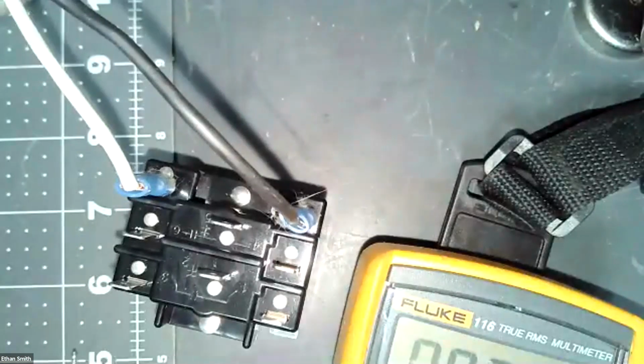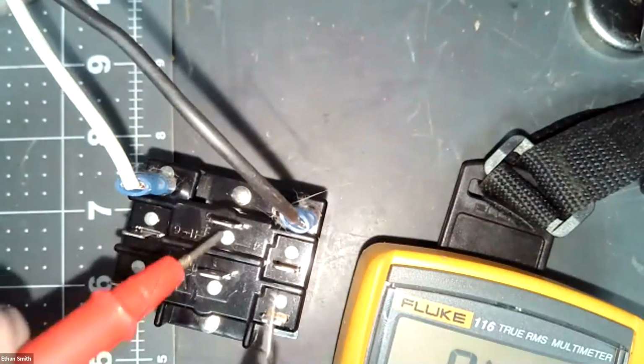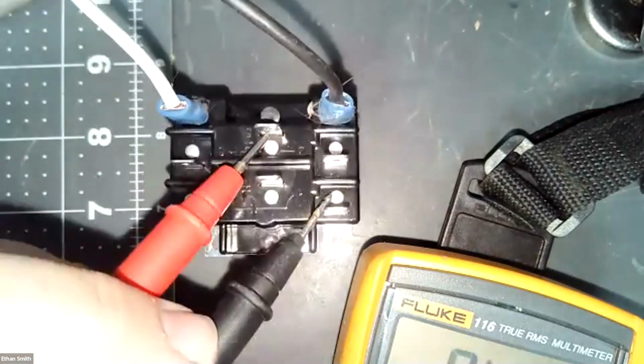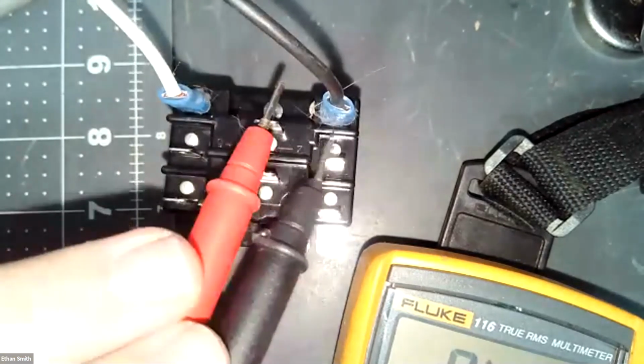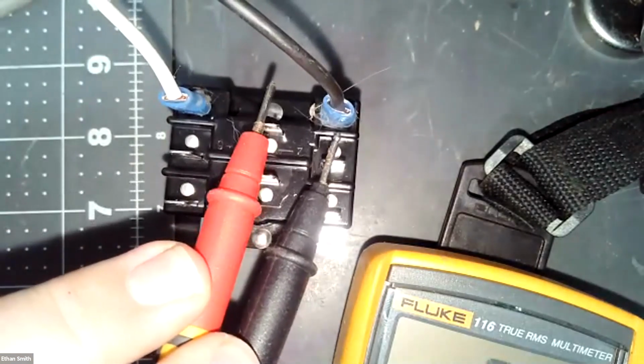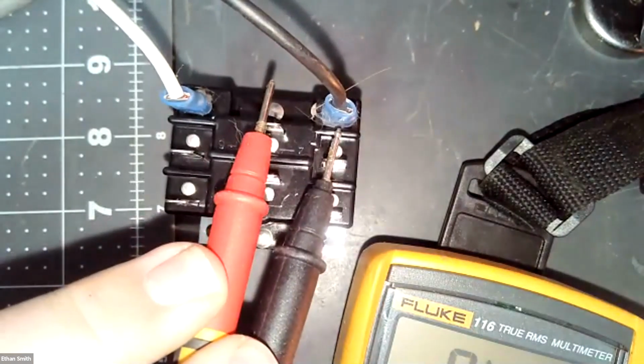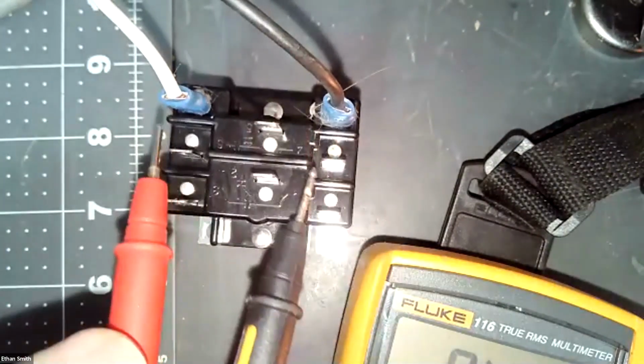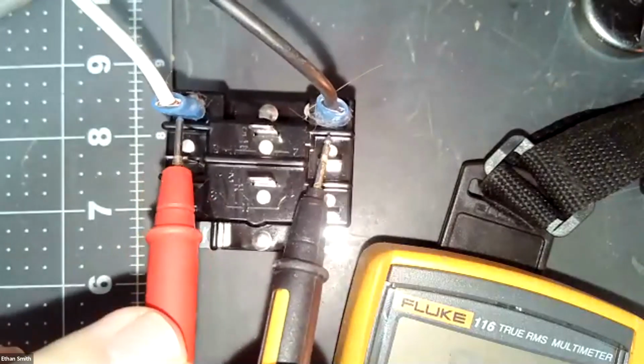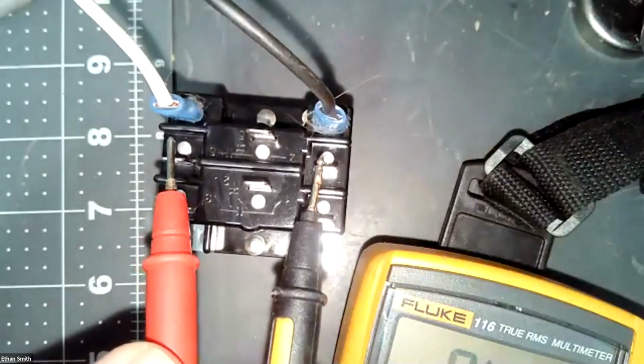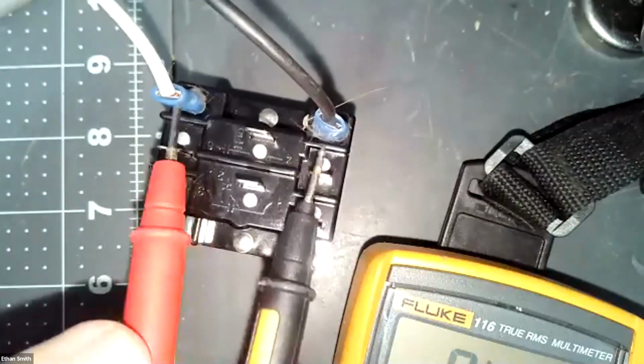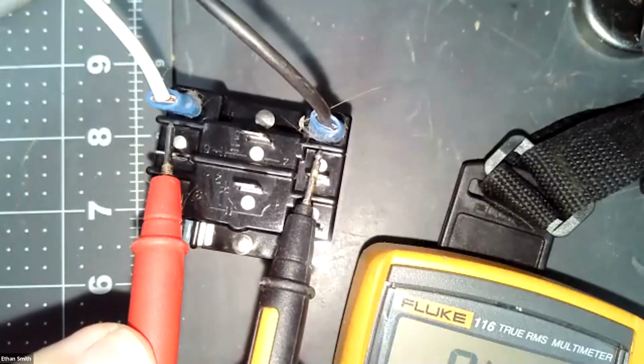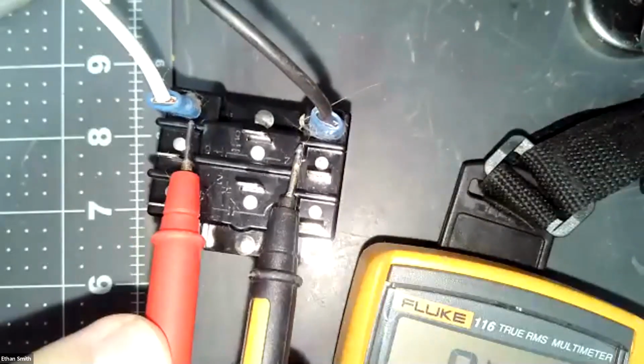Clear as mud? Okay, so there's two ways you can test switches. You can test them voltage-wise, or you can disconnect the loads off the switches and test with resistance. So we have our de-energized state. We've got no resistance on our normally closed. Once I energize that circuit, now I go to an open line there. Same thing here. Energized, I'm closed between those two leads. De-energized, I'm open. If I can keep my meter leads on them. Energized, de-energized. Cool?